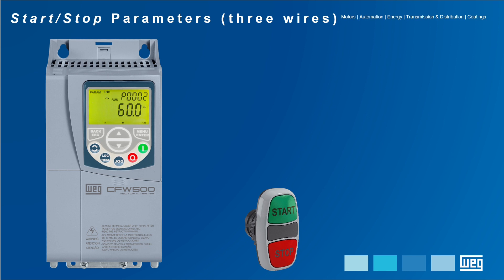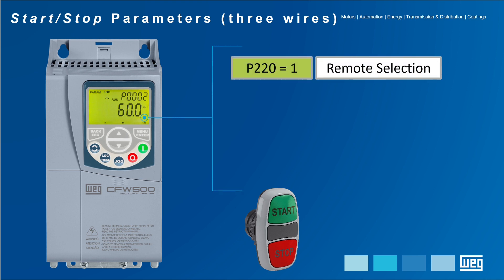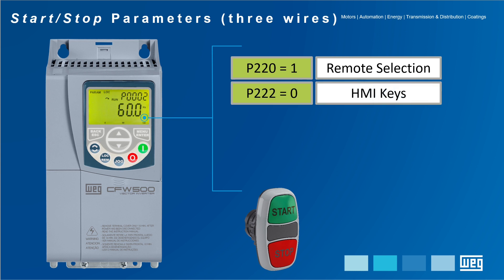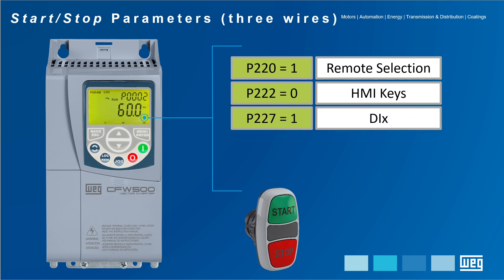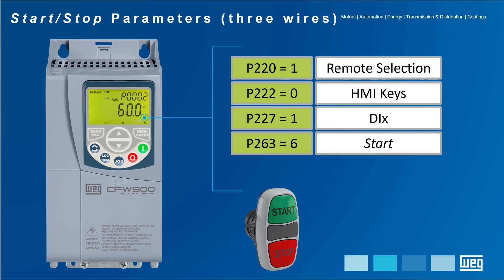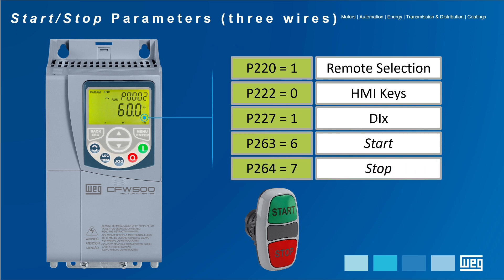You must set some parameters in the drive so the ON and OFF function by three-wire command can be executed. In this example we recommend P220 to 1 for remote selection, P222 to 0 for remote speed reference by HMI, P227 to 1 which defines the source for the RUN/STOP command in the remote situation via digital input, P263 to 6 which is the function of digital input DI1 for the START command, and finally P264 to 7 which assigns the function of digital input DI2 as STOP.